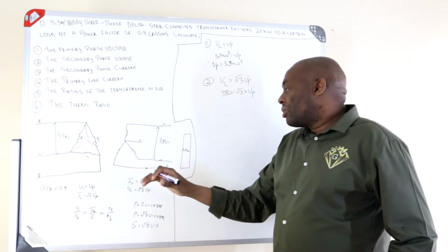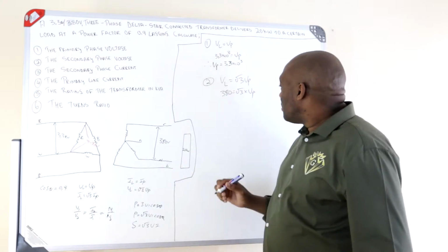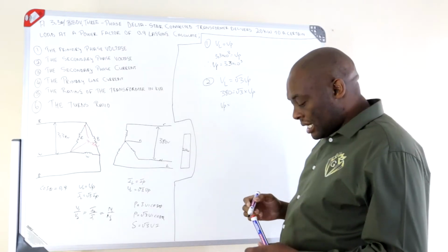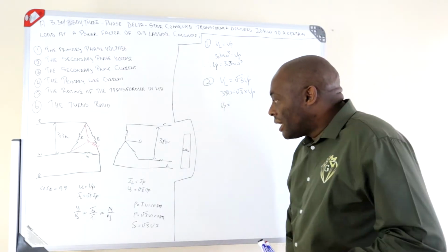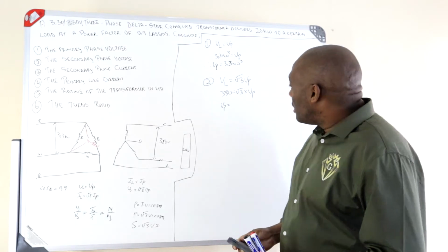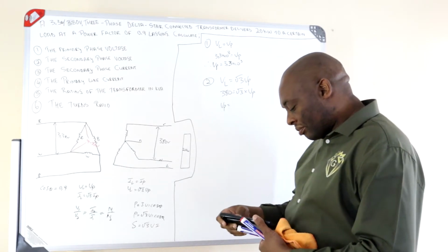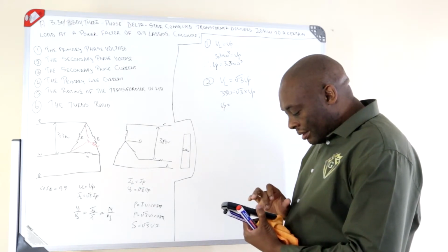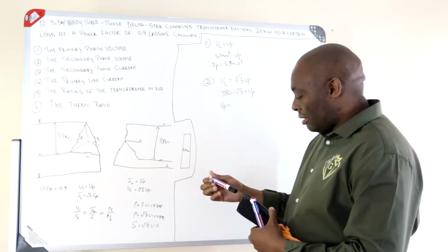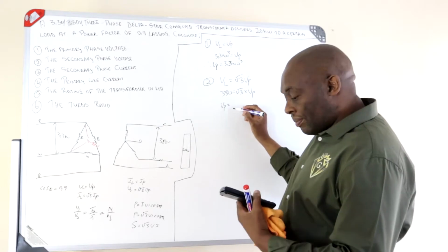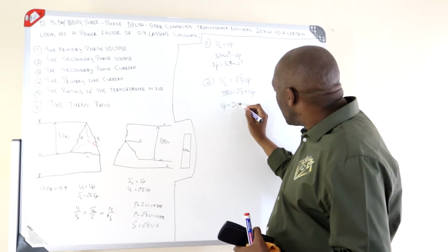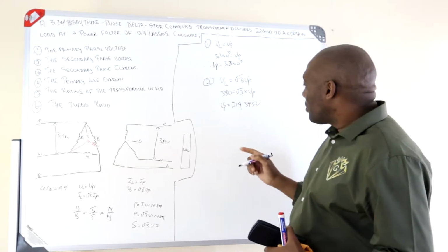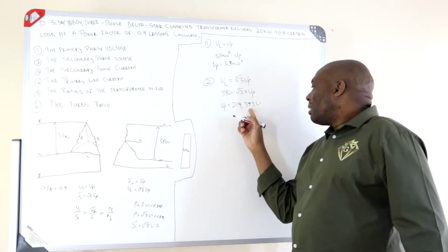That's why in this drawing here we went on our secondary side. Therefore, V phase will be equal to your 380 divided by the square root of 3. Let's calculate together and see if we'll have the same answer. It's 380 divided by the square root of 3. Therefore, our V phase here will be 219.393 volts. I'm using 3 decimals after the comma.